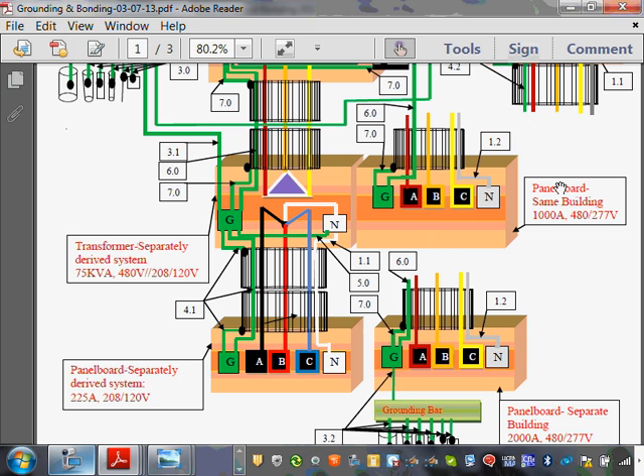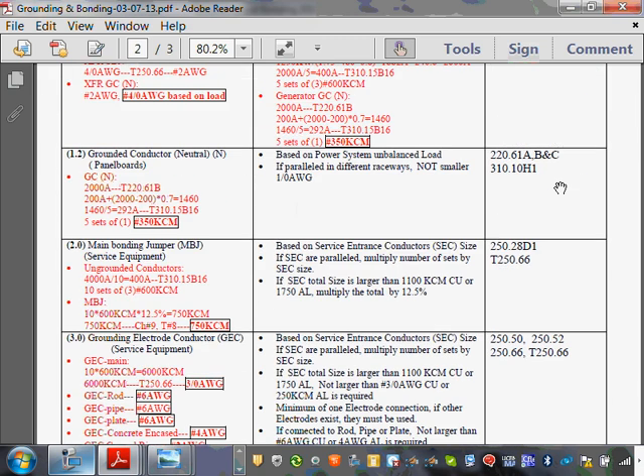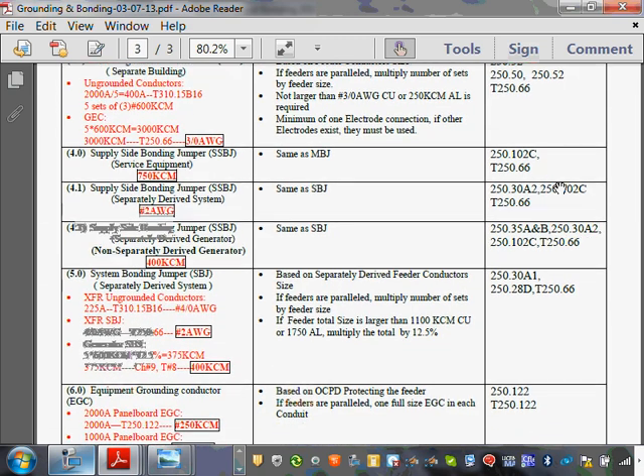So as long as this is my system bonding jumper, let's size the system bonding jumper. Very quick here, to 5. And if you look at 5, here's my system bonding jumper, that's what they call it. Not separately derived, system bonding jumper at the separately derived system.